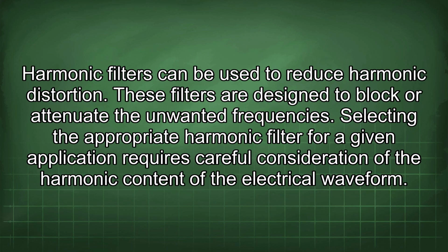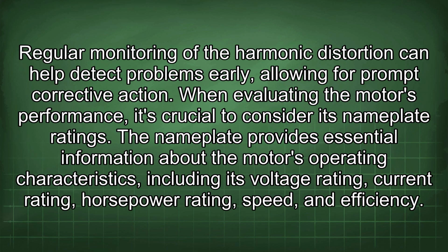Harmonic filters can be used to reduce harmonic distortion. These filters are designed to block or attenuate the unwanted frequencies. Selecting the appropriate harmonic filter for a given application requires careful consideration of the harmonic content of the electrical waveform. Regular monitoring of the harmonic distortion can help detect problems early, allowing for prompt corrective action.